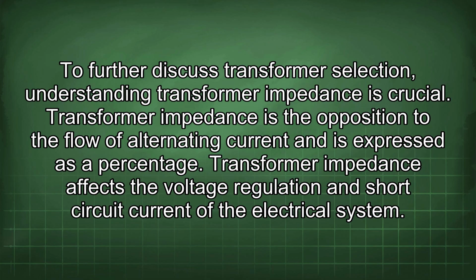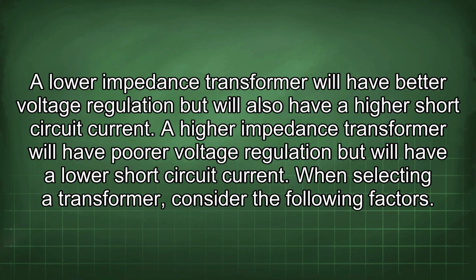To further discuss transformer selection, understanding transformer impedance is crucial. Transformer impedance is the opposition to the flow of alternating current and is expressed as a percentage. Transformer impedance affects the voltage regulation and short-circuit current of the electrical system. A lower impedance transformer will have better voltage regulation but will also have a higher short-circuit current. A higher impedance transformer will have poorer voltage regulation but will have a lower short-circuit current.